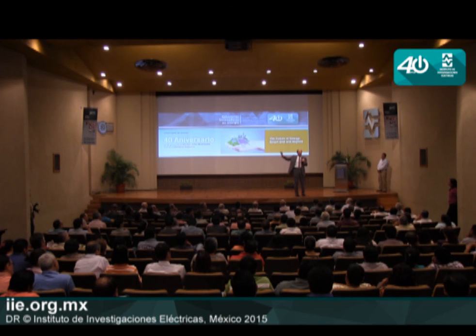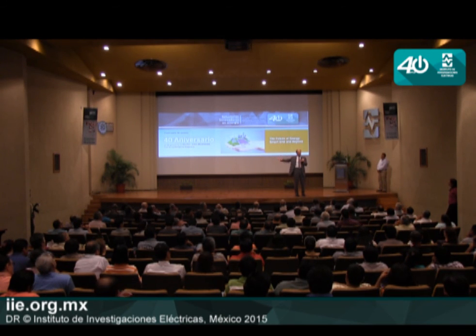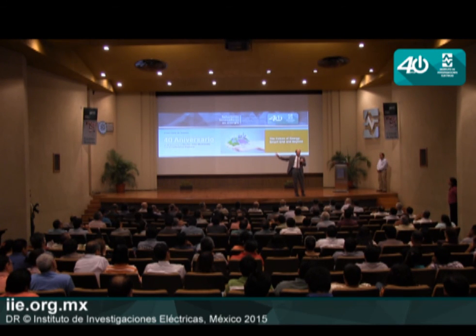We have what we call intelligent line monitoring, sensors you add on the distribution feeders. So I think what's going to happen with the emphasis on distribution and DMS, it requires us now to do more with putting sensors in the substations and feeders, because our DMS can't do anything unless it first has real-time information, telemetry coming back. But we are retrofitting it - the sensor is there, and we are adding them on.